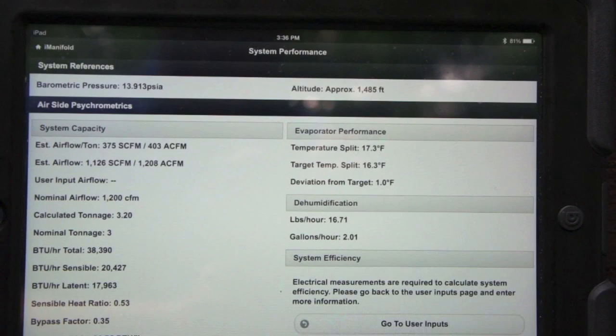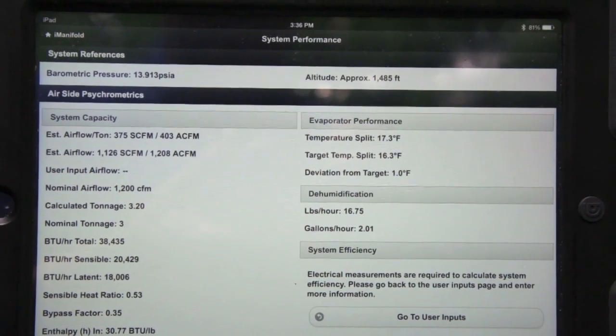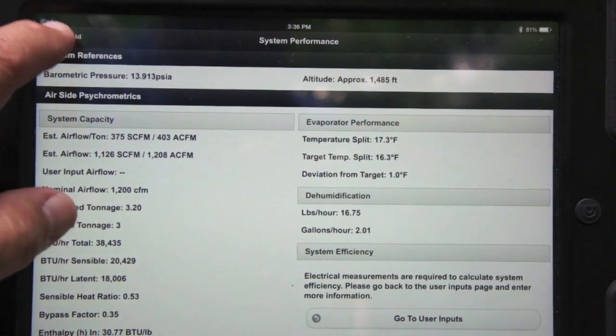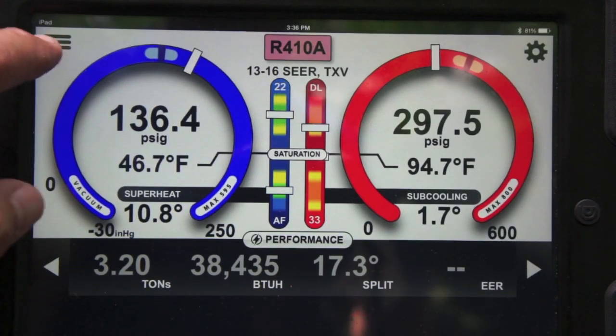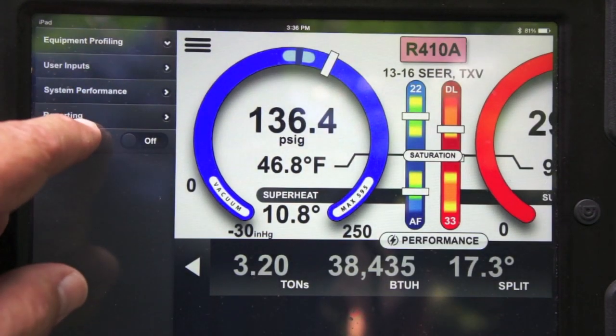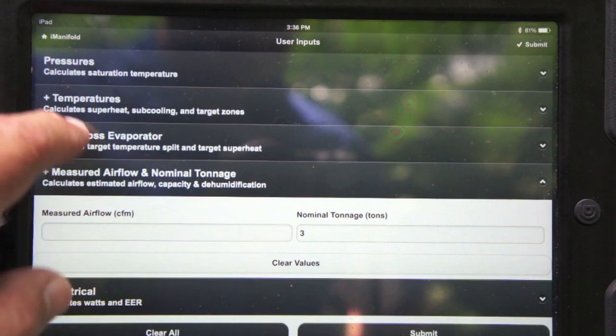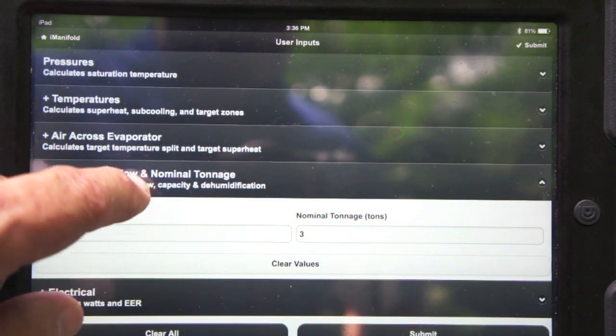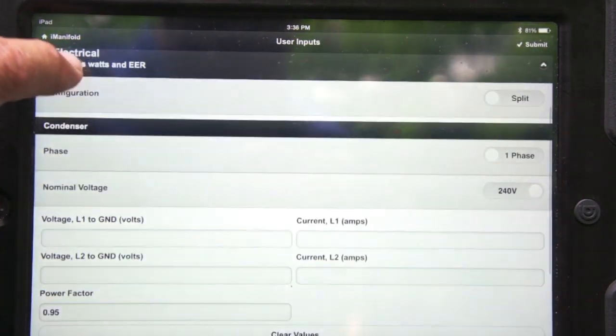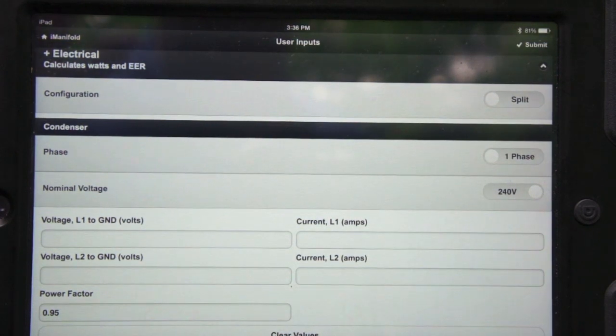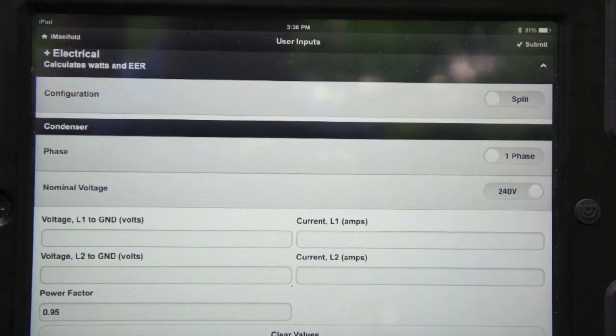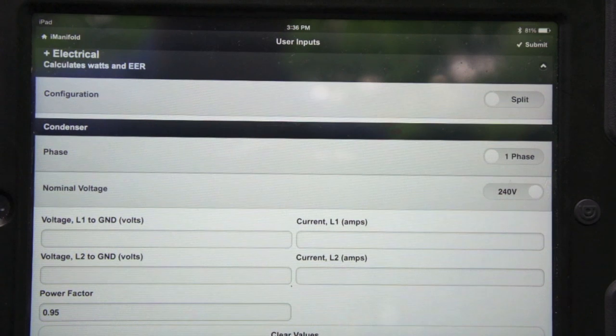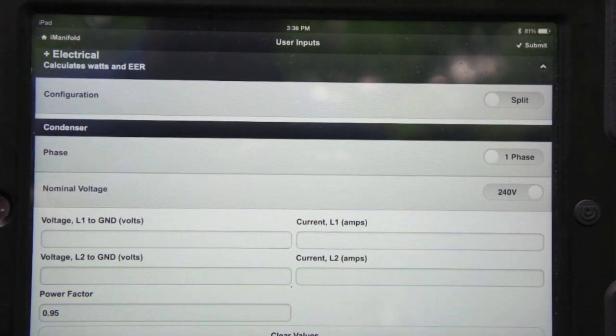What that leaves us with now is simply one thing to put in, which I'll go back to user inputs. Which is going to be our electrical, and that is it, and we'll have BTUs and EER. So we're going to let the system settle out for a minute. We literally just started it, and I'll go ahead and start making some electrical measurements, and we'll get those input and see how the system's operating.